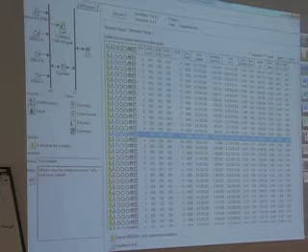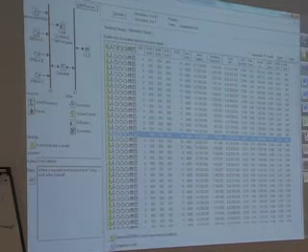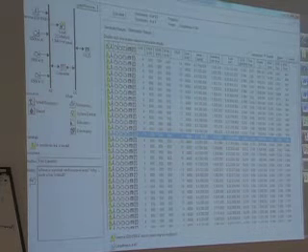So you're saving something like $130,000 a year in operating costs. And the fuel consumption is going from, I can't read this, 1.09 million to 885,000 liters per year. So that's the kind of big picture question that we like to use Homer for. Well, should we be thinking about a 4th turbine?